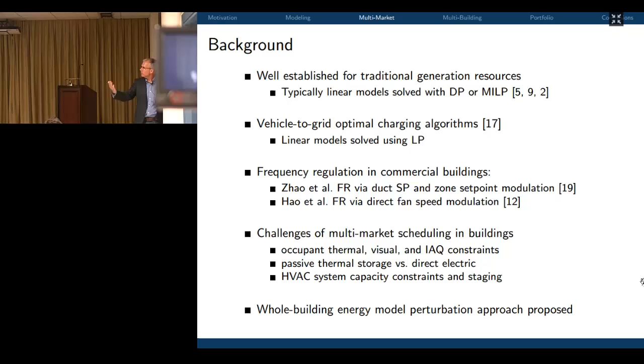Passive thermal storage is not the same as electric storage. With a battery, you charge and discharge it. But the dynamics of charging a building as a battery, cooling it down and letting it warm up, is very different. I can take all night to cool this thick wall, and come in tomorrow at 8am to a nice cool wall. But if I try to suck out all that stored cooling in one hour, I can't, because the heat transfer is natural convection, depending on inside room temperatures I can't control. It's very different, and we also need to consider that HVAC systems have capacity constraints — they don't have infinite capacity to provide cooling.